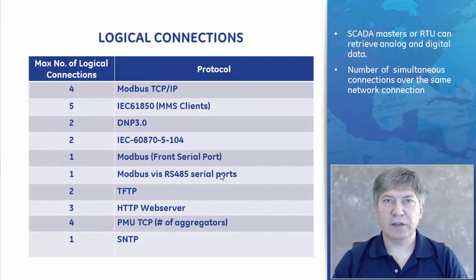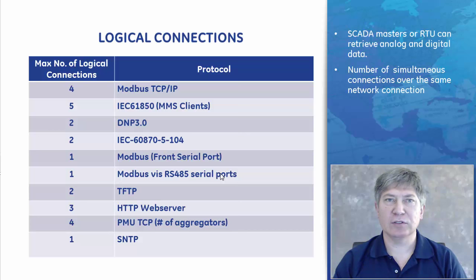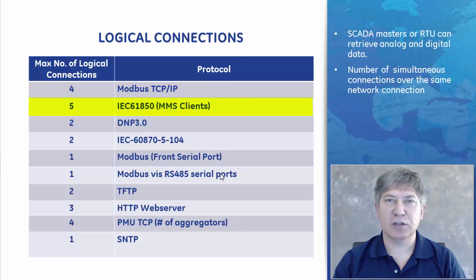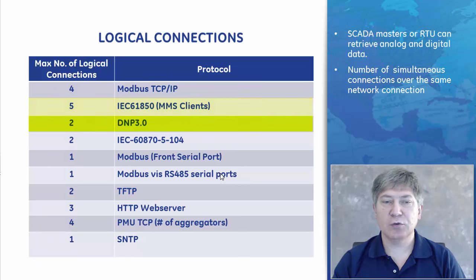In utility and industrial applications, multiple SCADA masters and RTUs constantly retrieve pertinent information in the form of analog and digital data. This table acts as a guide showing the number of logical connections per protocol. For Modbus TCP/IP, we have a maximum of four logical connections. IEC 61850 has a maximum of five connections. DNP3 has two, and so on, all the way down to SNTP.